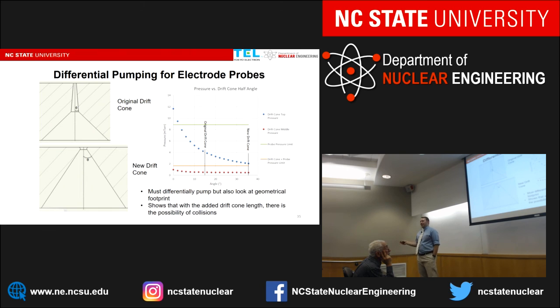However, that's not the only distance. If you have the drift cone, you now have a whole lot of extra distance. So that's what the orange line is: based on the mean free path of the ions through the drift cone and through the probe, that's kind of the operation limit. Now, it's not perfect because for those lines I was using a single value, but the pressure is changing all the way down this drift cone. But what this plot shows us is the middle of the drift cone.